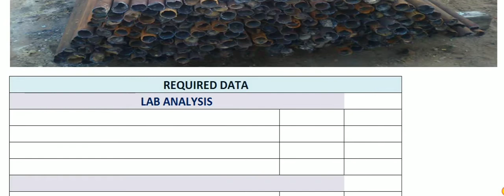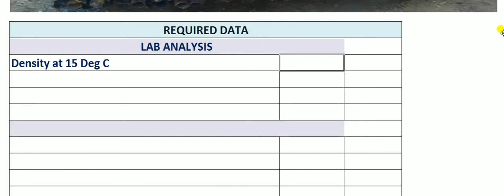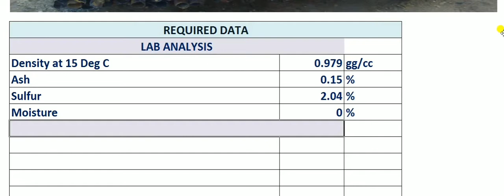Collect a fuel oil sample and give it to the lab for analysis. First is the density at 15 degrees centigrade, then the ash content, sulfur content, and moisture, which will be around 0 only. These we should analyze, and next we require the flue gas parameters.